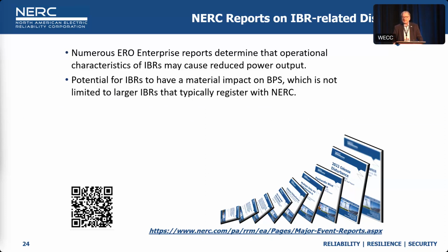We had an event that occurred on the system out east in July of this year, where a line arrestor failed, single phase to ground fault on a 230 kV line, cleared in 3 cycles. So I think any protection relay engineer would say, awesome, the maintenance guys, the breakers worked correctly and they worked fast like they were supposed to. But even clearing in 3 cycles, which is 1/20th of a second, we had 1,550 megawatts of load instantaneously trip because of that 3 cycle single phase to ground fault on a 230 kV line. As we went to look at it more, a lot of that was data centers.